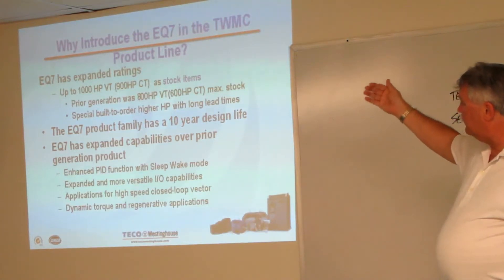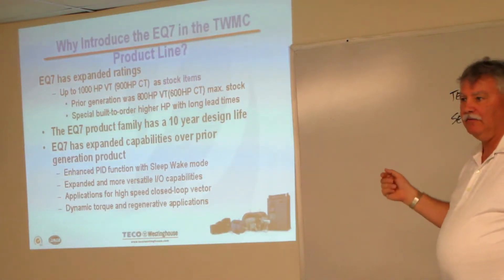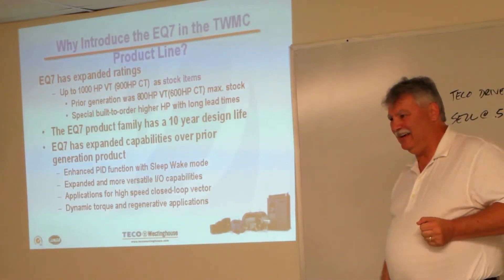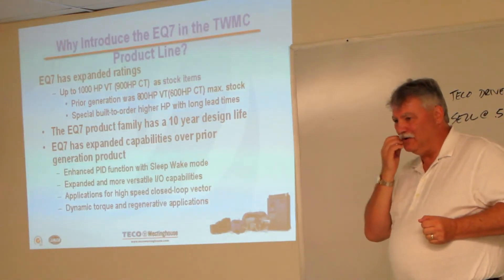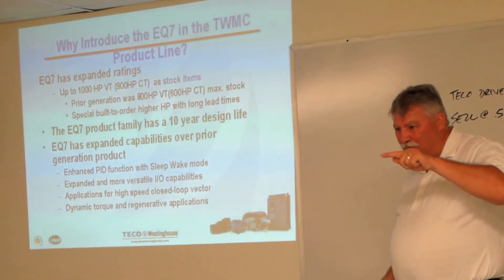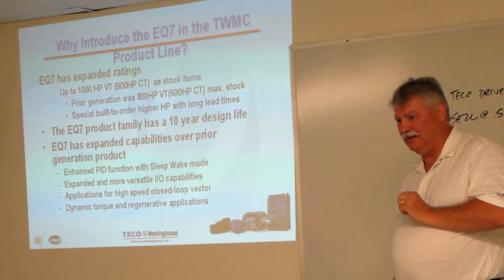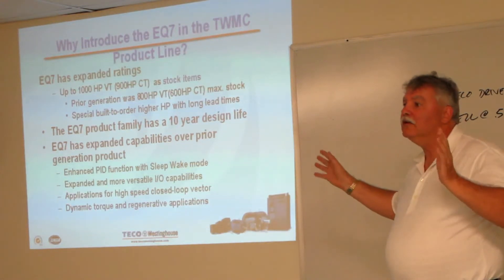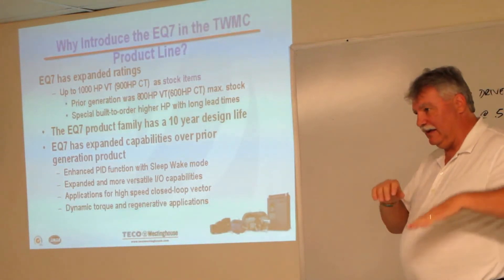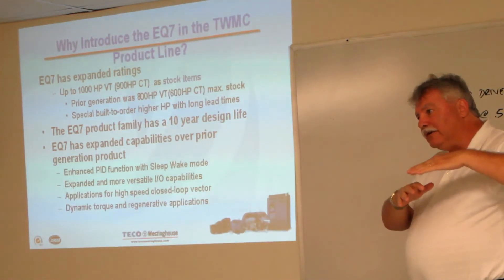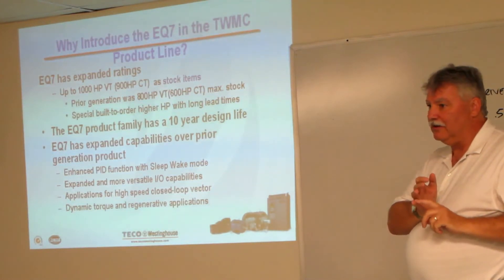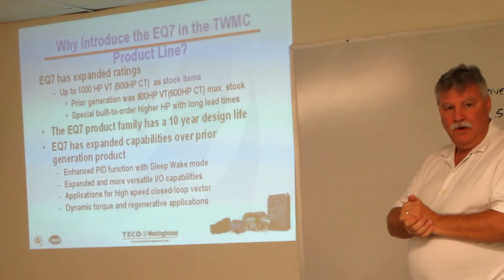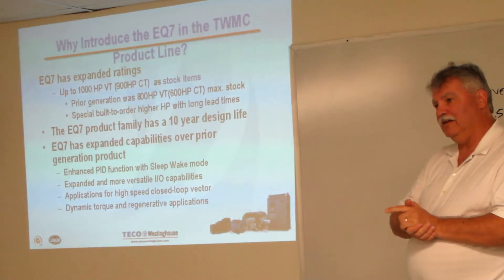One of the things we did with the PID function: do you ever see the situation where the PID conditions say you don't really need any action from the motor, and it's just crawling along at a real slow speed not doing much? We have the option to say, instead of turning the motor slowly, just put it to sleep — let it go to rest. Meanwhile in the background it's monitoring, and when pressure or demand flow changes and the motor is called to do actual work, it will wake up. So we can put that sleep/wake capability in on the drive — that's energy saving.